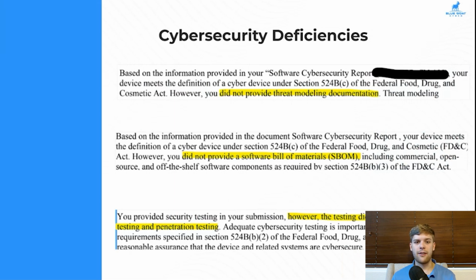Now, here are a couple of examples of cybersecurity deficiencies. We're missing threat modeling documentation. We're missing a software bill of materials. We're missing vulnerability testing and penetration testing. This bottom one is especially important to look at. You provided security testing in your submission. However, the testing did not include vulnerability testing and penetration testing.